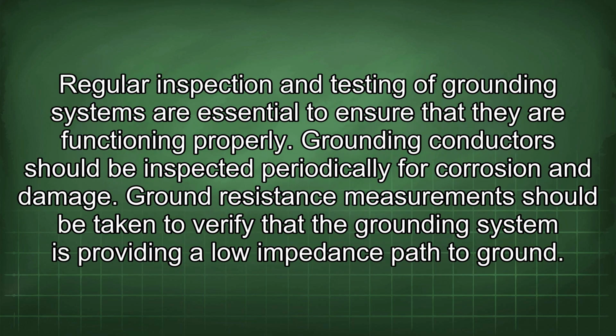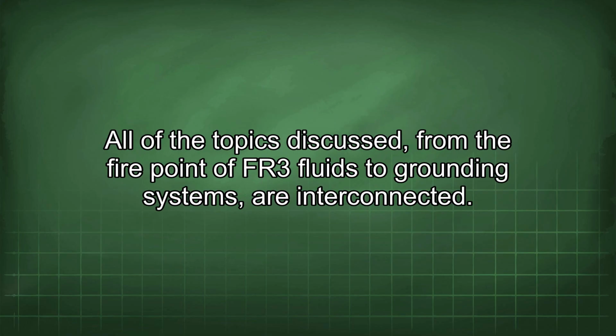Regular inspection and testing of grounding systems are essential to ensure that they are functioning properly. Grounding conductors should be inspected periodically for corrosion and damage. Ground resistance measurements should be taken to verify that the grounding system is providing a low impedance path to ground. All of the topics discussed, from the fire point of FR3 fluids to grounding systems, are interconnected.